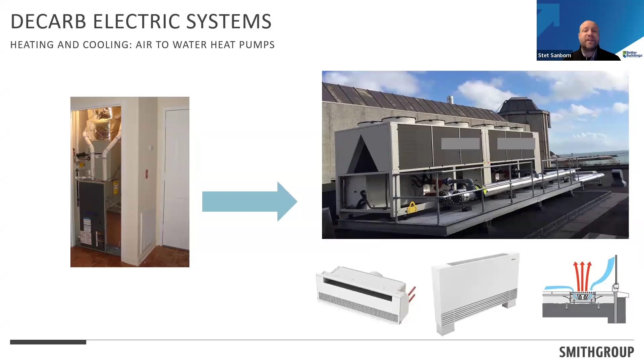One of the nice things about air to water heat pumps is they can do what we call a temperature reset. They can go to a lower supply water temperature for heating in the shoulder seasons, saving your occupants or the building operator a ton of money.